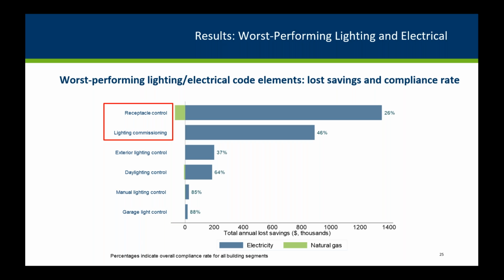This element is often not documented well on electrical drawings. As this is a relatively straightforward hardware component, it would seem that many design teams are either unaware of the receptacle control requirement or have chosen not to comply. In comparison to mechanical commissioning, lighting testing and commissioning appears to be even less widely implemented. This may be because it is a newer practice, given that advanced controls are newer to the industry.